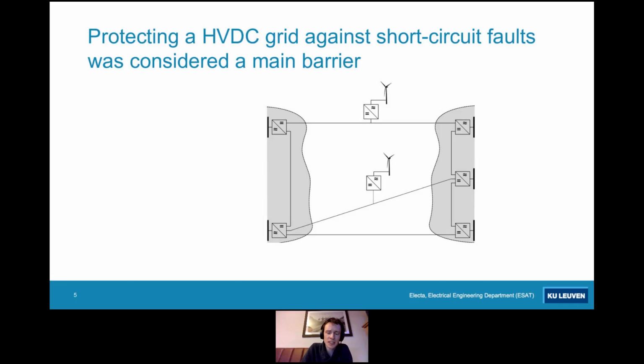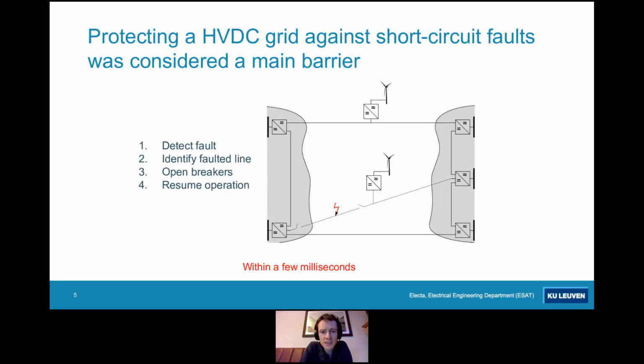So to recapitulate, what we need to do in case of faults is, if we have a fault, we need to detect it using the voltage and current measurements put at each end of the cable. Then we need to identify the faulted line so that we don't unnecessarily trigger breakers, or shut off a larger part of the grid than is needed. We need to open these breakers, and then we can resume operation. And all of this has to happen within a few milliseconds.